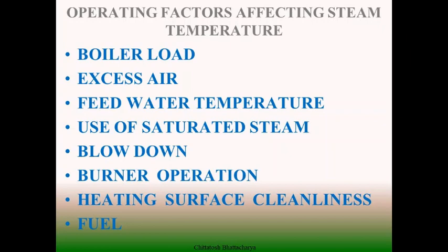Besides that, burner operation is an important parameter. We can arrange the burner and operate the burner in such a way that we can manage the distribution of heat between superheaters, reheaters and water walls. If we want more heat to be absorbed in the water walls compared to superheaters, it can be done. So we have to see how the heat absorption is distributed with the burner operation, that affects the steaming parameters.